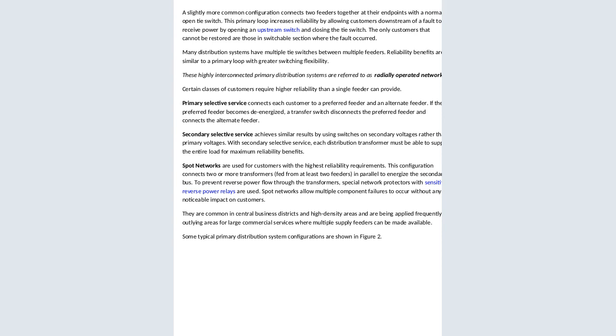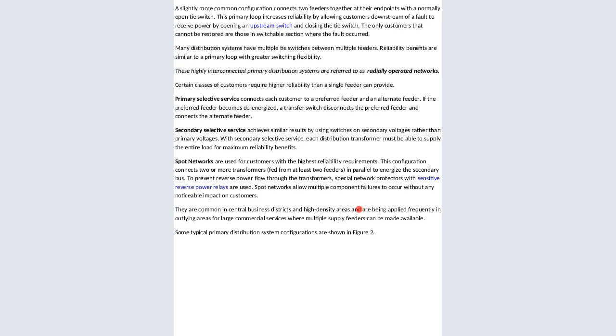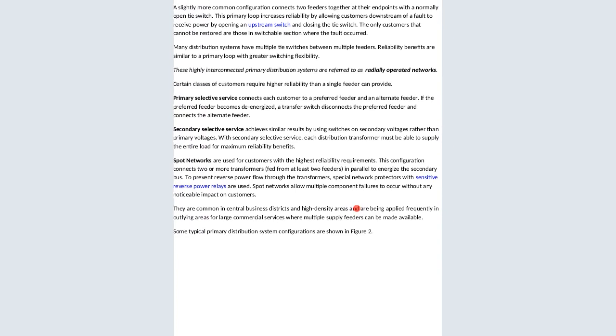Then we have secondary selective service, which achieves similar results by using switches on secondary voltages rather than primary voltages. So with secondary selective services, each distribution transformer must be able to supply the entire load for maximum reliability.